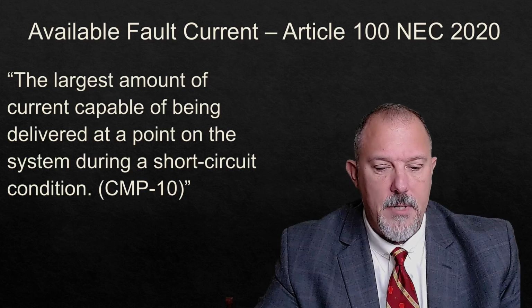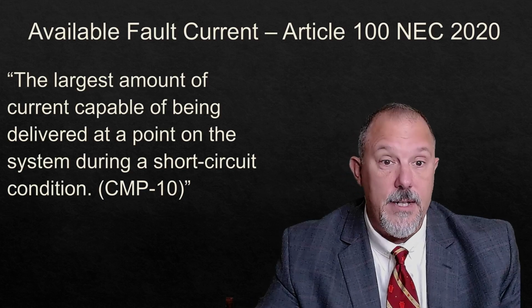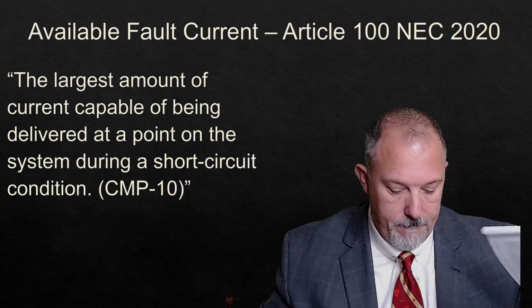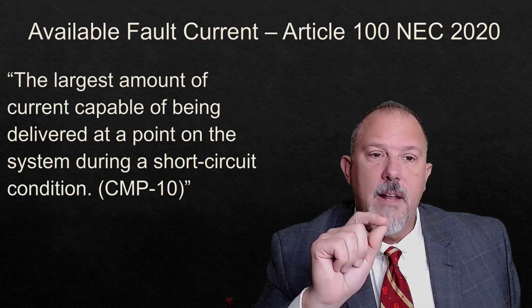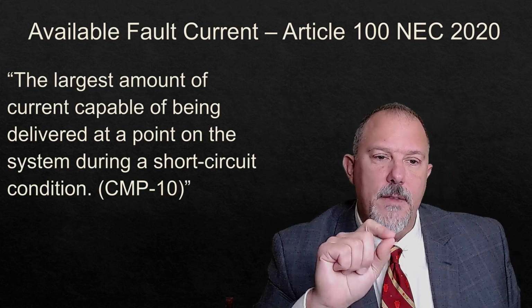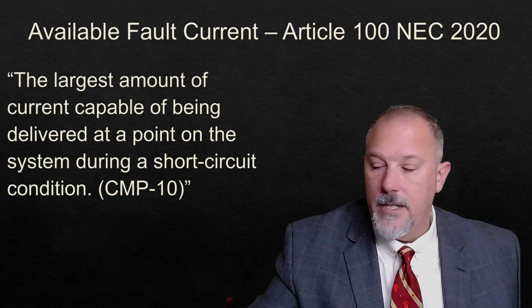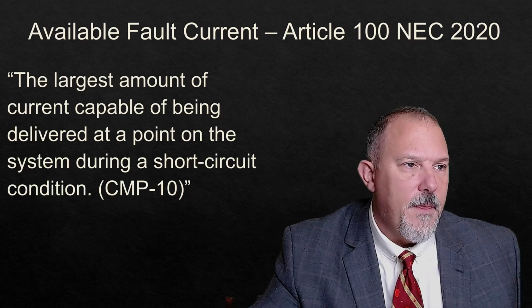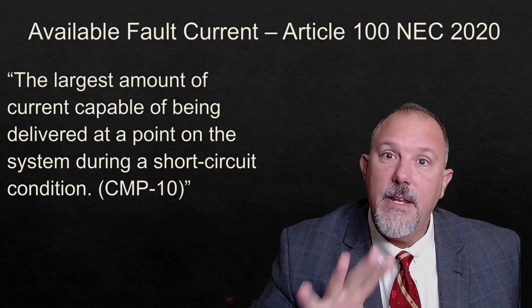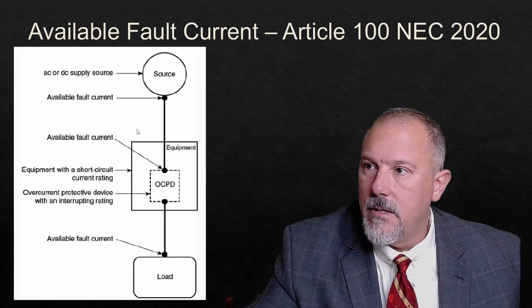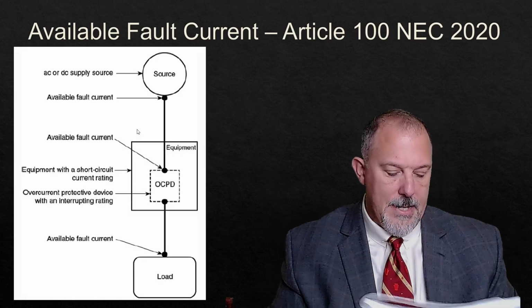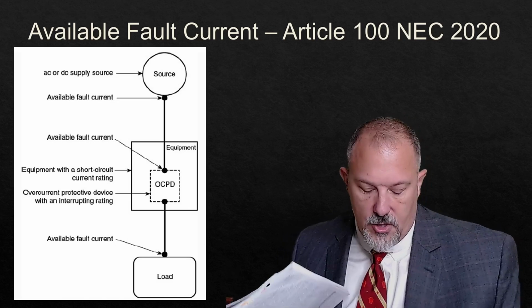This is, I believe, a panel 10 definition. Yes, it is. CMP 10. Look at that. All right. So the largest amount of current capable of being delivered at a point on the system during a short circuit condition. That's an important thing to know. And they even give us a diagram. Let's take a look at the diagram. And the diagrams are identical between the two versions.